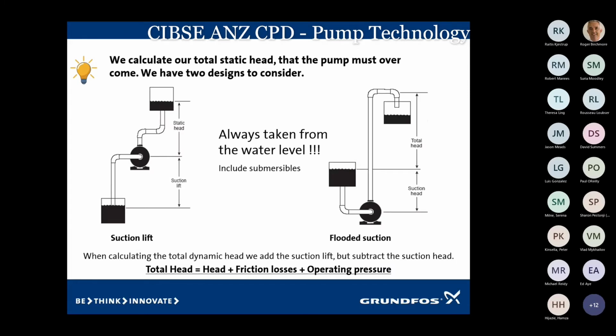If we look at the water supplies and we're having to calculate our head, then if the water is below the pump, we have our static head now is from the water level where we're pulling water from, straight up to wherever we're delivering the water. So on the left-hand side, the picture on the left-hand side, we've got a suction lift, and then we have a static head. It's the total of those 2 guys, plus the losses in the pipework to give us our head. When we have a flooded suction, we take the level of the water above the pump, and then that's the start point to the delivery point is where we're trying to push it into.